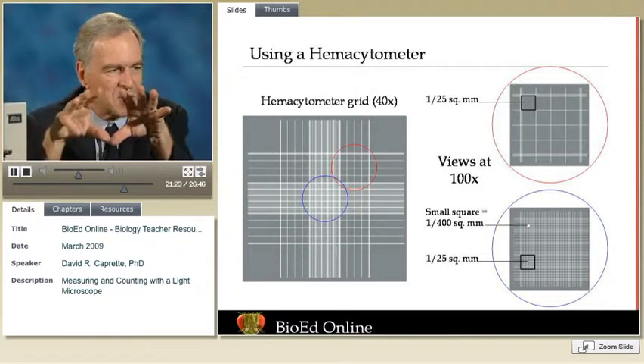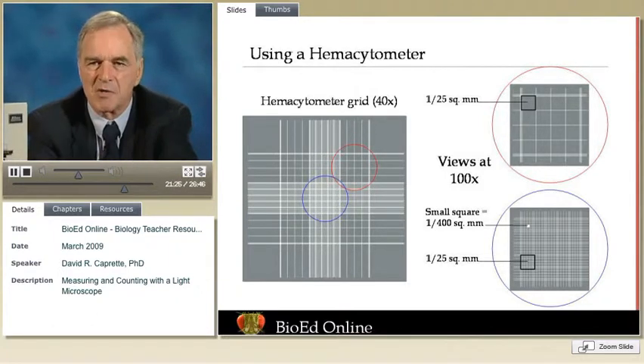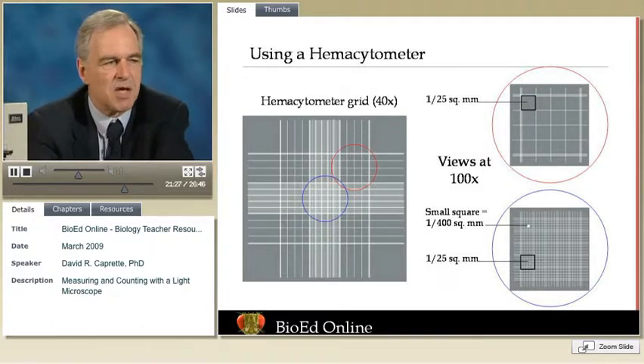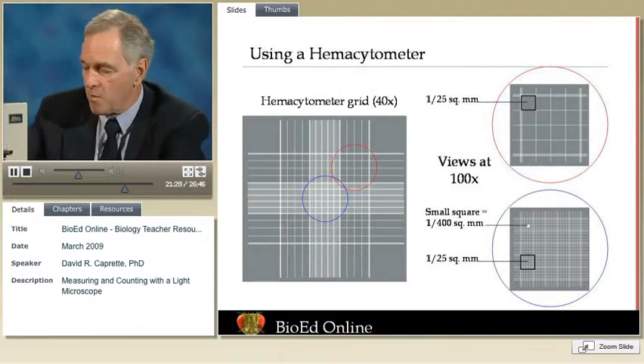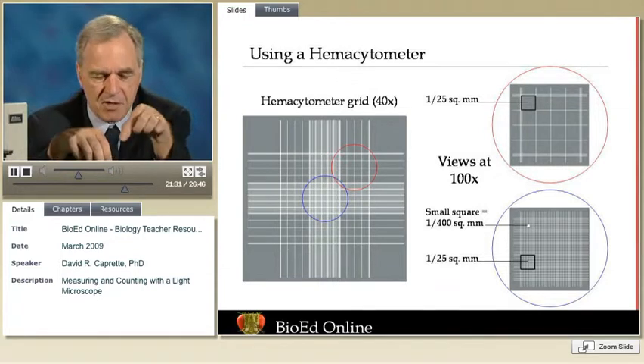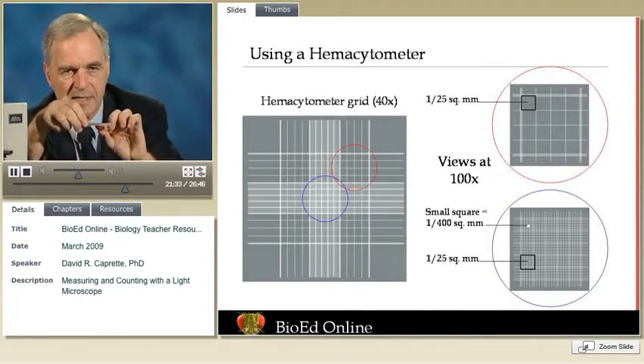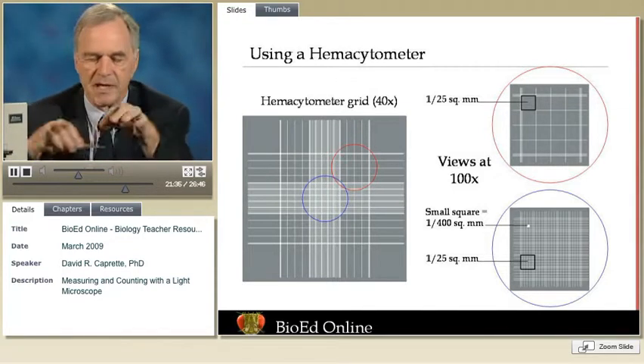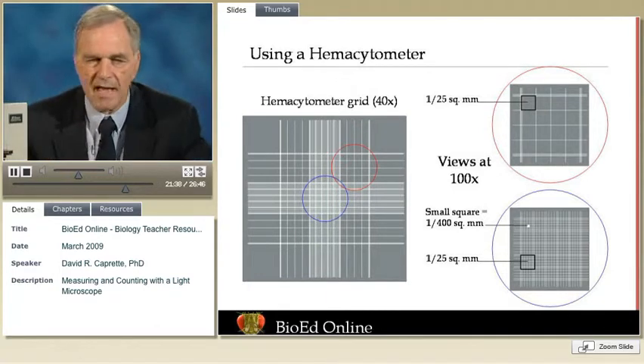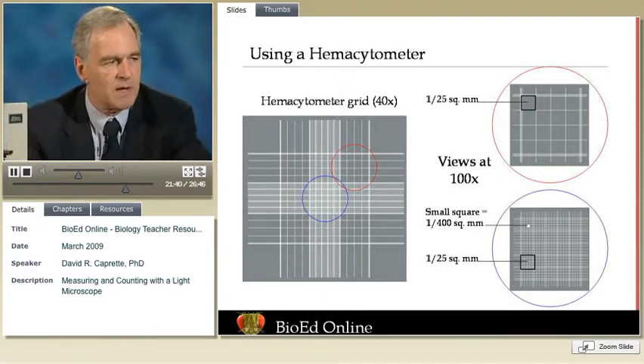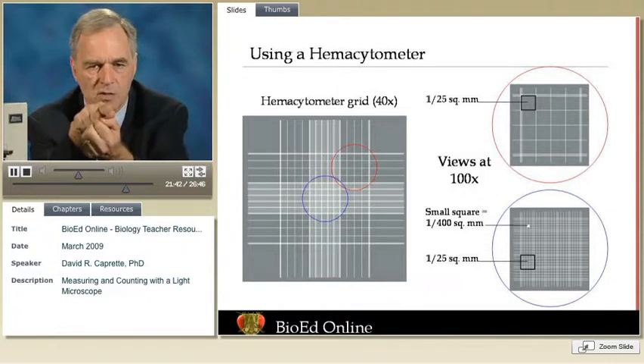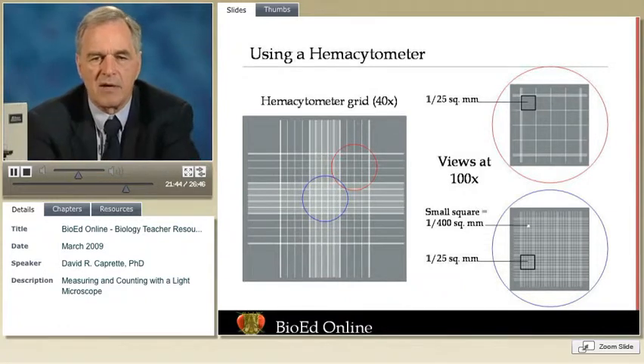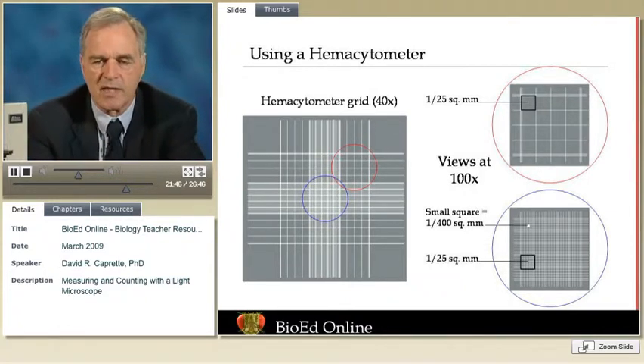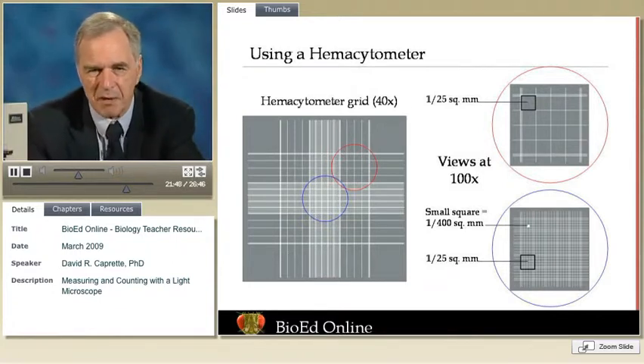There are 9 big squares. Each of those squares is a square millimeter. So you might be thinking, aha, what we have is a calibrated surface area. We have a calibrated depth. If you put some liquid underneath the cover slip and count everything in that drop of liquid that happens to be under one of those large squares, you've counted all the materials that are within 1/10 of a cubic millimeter.